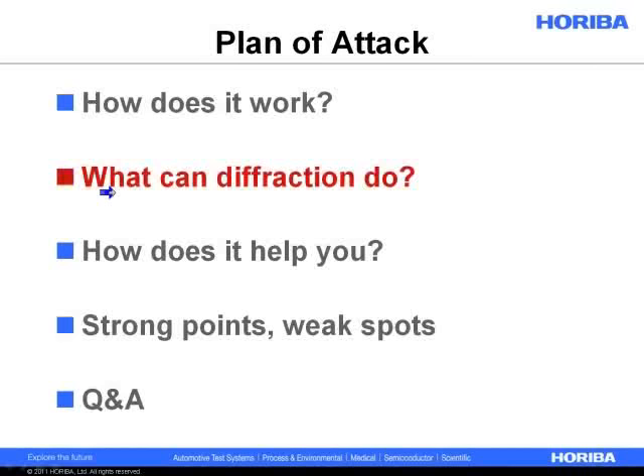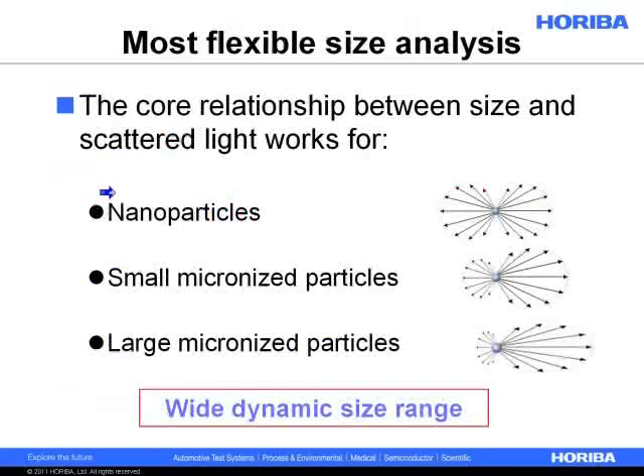Now we're going to move on to what are the limits of this measurement. One of the reasons diffraction has become so very widespread and popular is because it's a very flexible size analysis. The largest part of that is it can measure so many different sizes of materials. Dynamic light scattering is really just nanoparticle-only, whereas laser diffraction can go down as far as 30 nanometers and up as far as several millimeters. It's a very wide dynamic range.